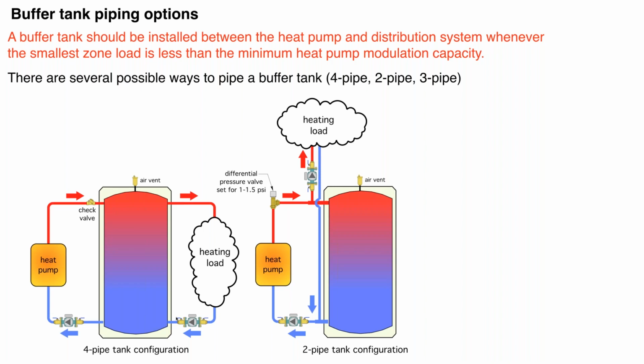And I started studying it more and thinking about it and reading more about it. And there are some advantages to this. One of the advantages is what's called direct to load transfer. If the heat pump and the load are operating at the same time, with this configuration, it is possible to send heat directly to the load without first having to warm up the mass of the buffer tank. And that can be an advantage coming out of a setback condition, for example.